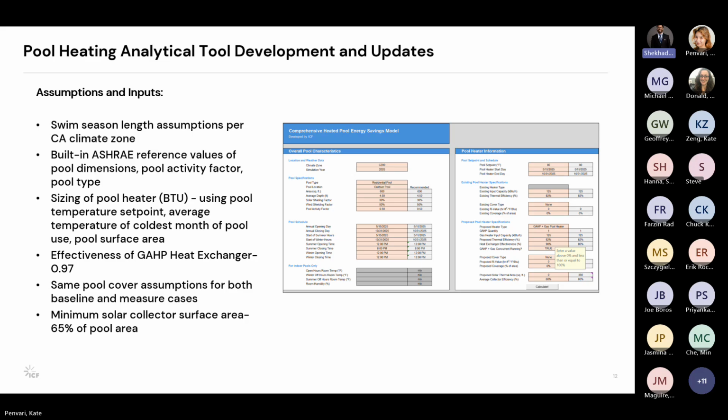Our previous GET studies demonstrated that it takes about 20 minutes to achieve steady state COP for given operating hours. So we assume that for the first hour when GAHP kicks in, the heating outputs and flow rates are about 2/3 in that first hour. As far as GAHP is concerned, another important assumption is related to heat exchanger effectiveness, which is significant in determining the energy saving potential.